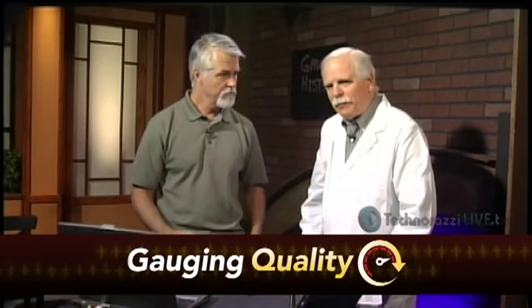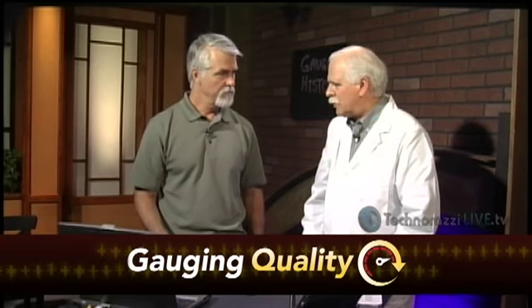How do you measure flatness and parallelism on the anvil in a micrometer? For flatness, we use an optical flat and a monochromatic light source. Flatness is a single surface measurement, so we put it right on the anvil and read the light bands that show up under the optical flat. We'll do that on both the anvil and then the other end, the spindle.